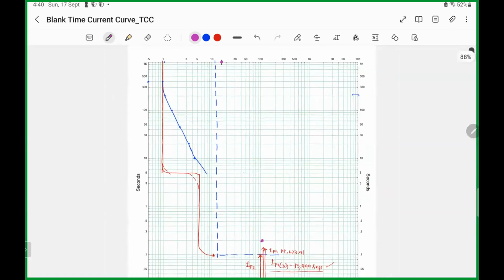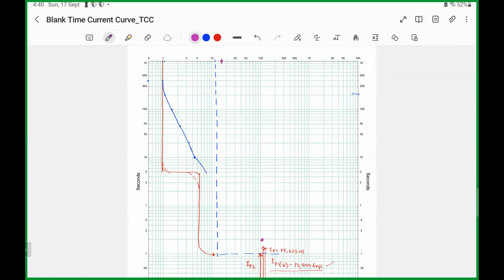So now, what we look for is the long time delay. Okay? The long time delay is usually around 5 seconds, 7 seconds, 8 seconds, or 10, depending on the characteristic or model of your low voltage circuit breaker. So I assume only 10 for now. Okay? So this one, you can project up to 10.